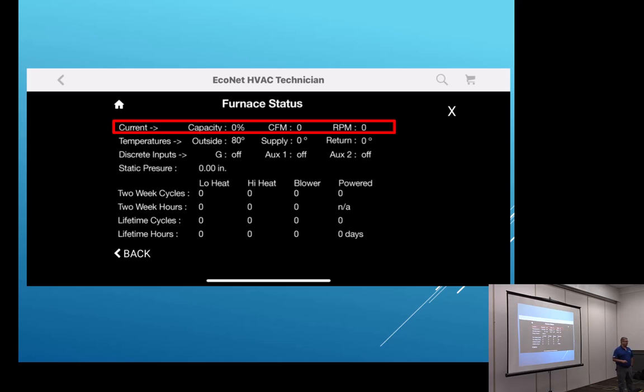Sometimes I get a bad rep. People say that I concentrate on this static pressure here. I really don't. I take all the information I can get together. I want this, I want the CFM, and I want the RPM. Just like when I'm charging a system, I'm not focused in on 10 degrees of subcool. I want to know what my temperature split is. I want what my superheat is. I want to know what my suction line temperature is. I want to know what my coil temperature is. And I use all of that information together to make a decision on what's going on with the system.